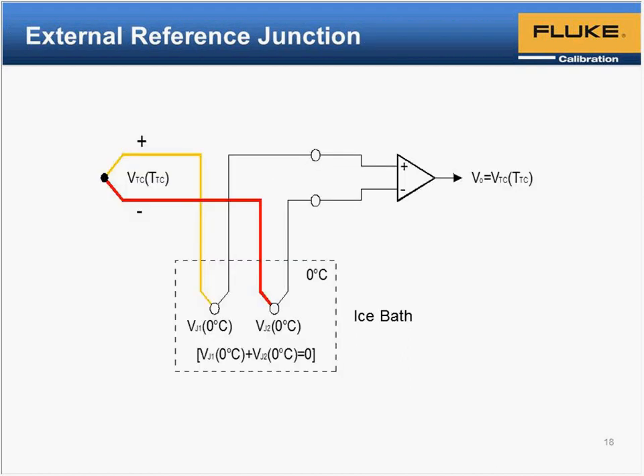Here's an electrical diagram showing how the wire in yellow and red is the copper wire down inside this bath. This junction connects the thermocouple wire to the copper wire. It doesn't have to be anything special. In our laboratory, for example, we just twist the two wires together and then apply solder to hold them together, and that's for calibrating. And we don't really worry about the fact that we're bringing in solder in this connection because this is an isothermal zone. The temperature is 0 degrees throughout this bath, so there's no chance of voltage being generated by these different materials mixing together.